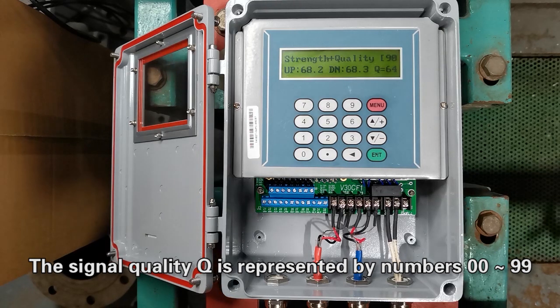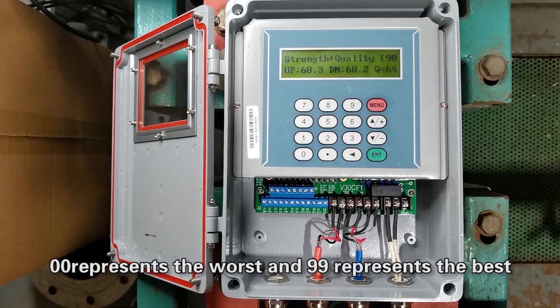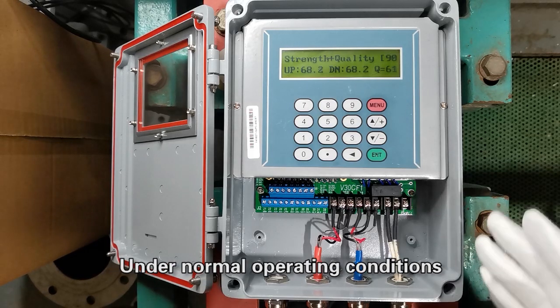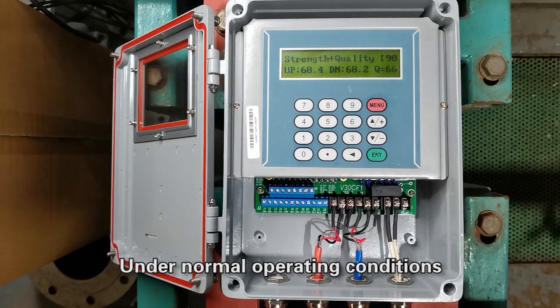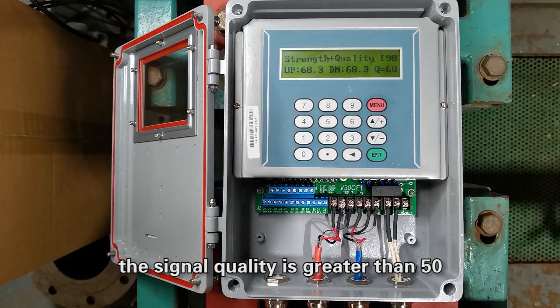The signal quality is represented by numbers 00 to 99. 00 represents the worst and 99 represents the best. Under normal operating conditions, the signal quality is greater than 50. Step 18. View transfer time ratio.